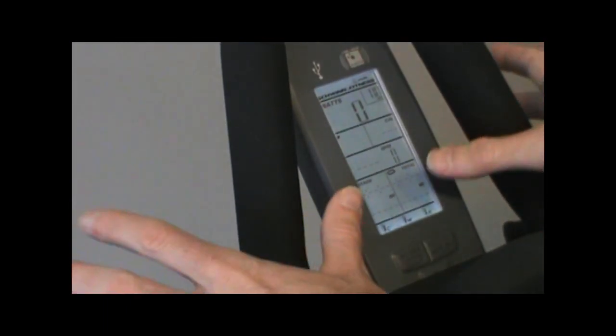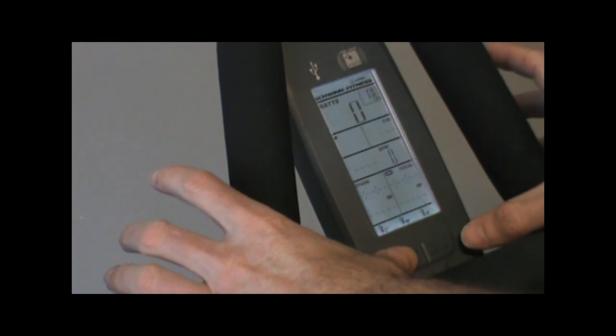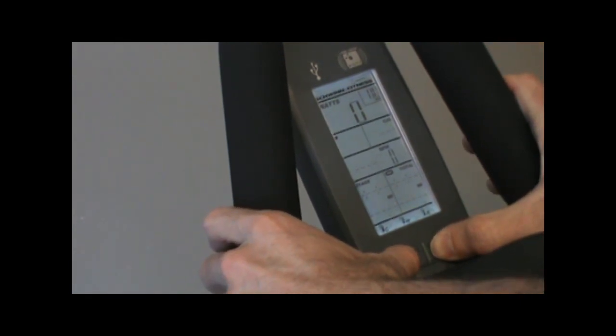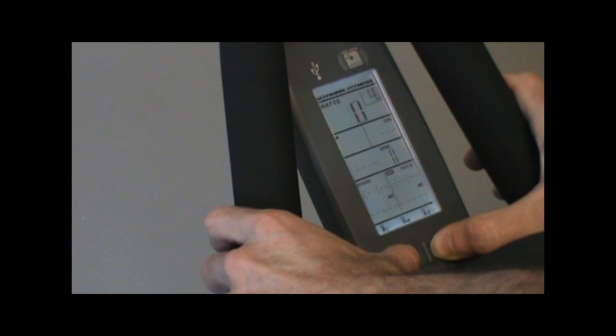Once your power sensor's active, you need to enter the service mode. Entering service mode, I'm going to hold down the stage and the average N button together for about 5 seconds. The screen will change to the service mode screen. Here it says units. What I'm going to do is scroll using the average N button until I see the word calibrate. That's where I perform calibration. Hit the light button. The light button is my enter button in the service menu.